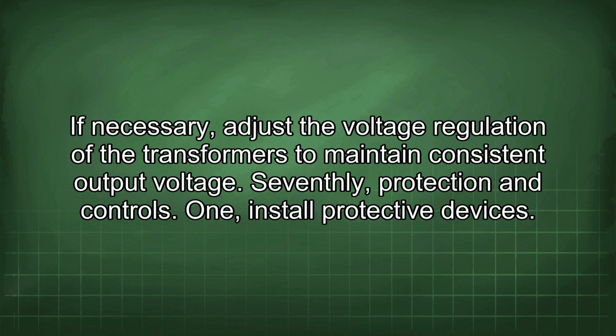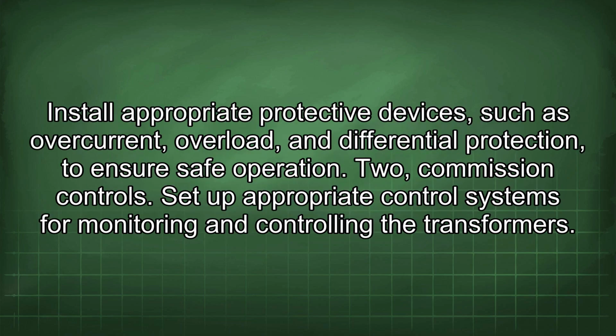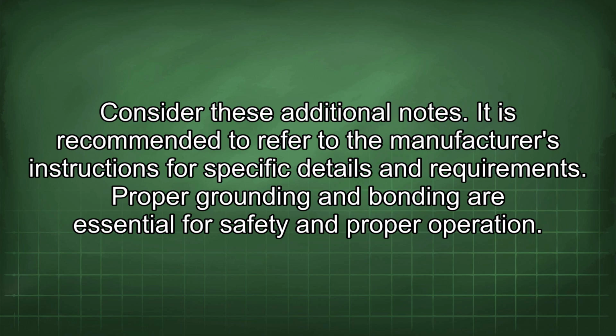Seventhly, protection and controls. 1. Install protective devices. Install appropriate protective devices such as overcurrent, overload, and differential protection to ensure safe operation. 2. Commission controls. Set up appropriate control systems for monitoring and controlling the transformers. Consider these additional notes. It is recommended to refer to the manufacturer's instructions for specific details and requirements. Proper grounding and bonding are essential for safety and proper operation.